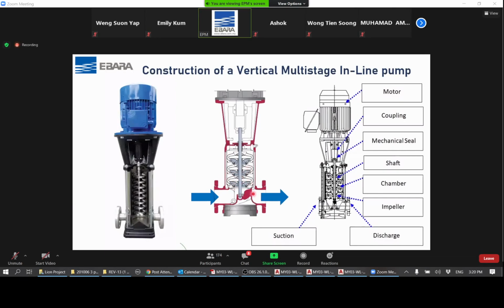So in each stage, it will build up pressure of around 1 bar or so, plus minus, and then it will move to the next stage, and the next stage will impart another 1 bar pressure by the centrifugal action, and the third, and so on. So then what happens is the water will now be channeled between the chamber of the pump and the outer casing out to your outlet pipe.